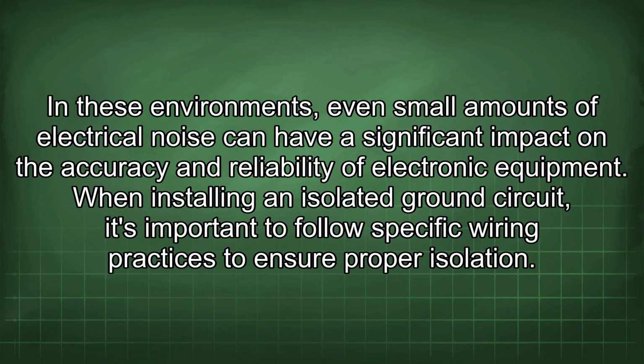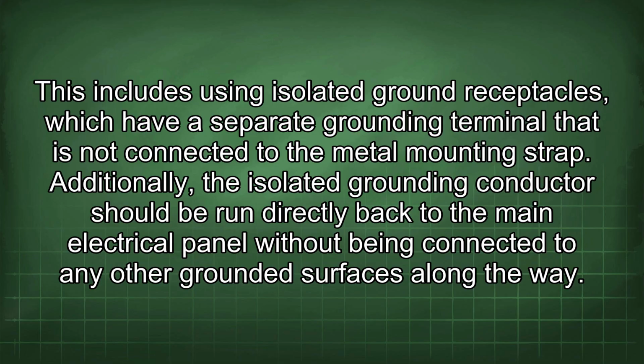When installing an isolated ground circuit, it's important to follow specific wiring practices to ensure proper isolation. This includes using isolated ground receptacles, which have a separate grounding terminal that is not connected to the metal mounting strap. Additionally, the isolated grounding conductor should be run directly back to the main electrical panel without being connected to any other grounded surfaces along the way.